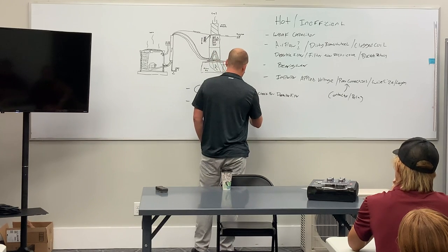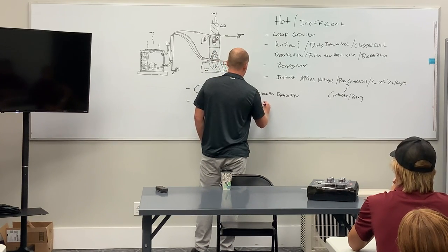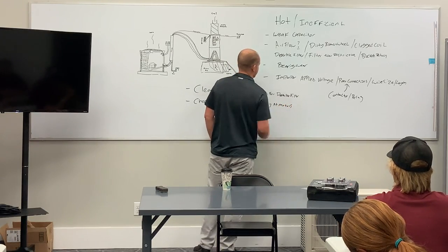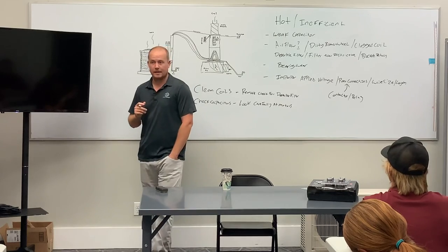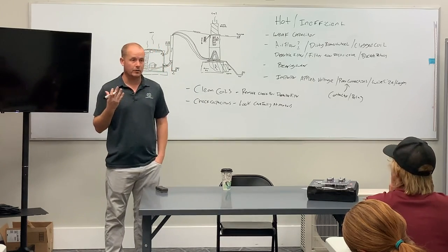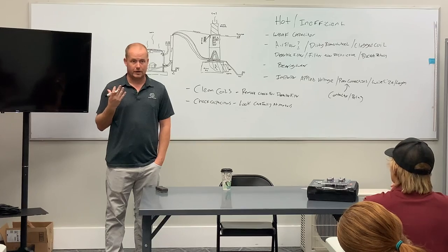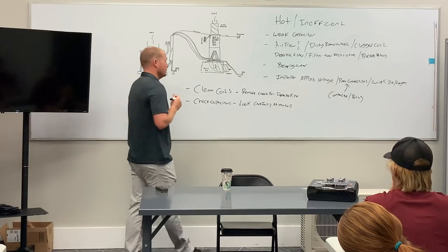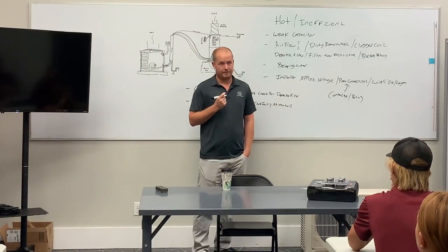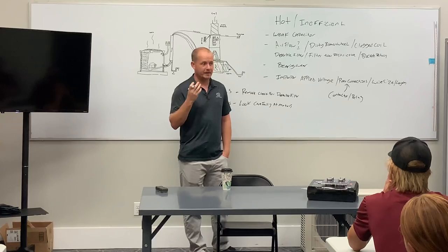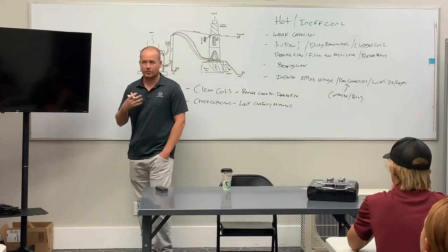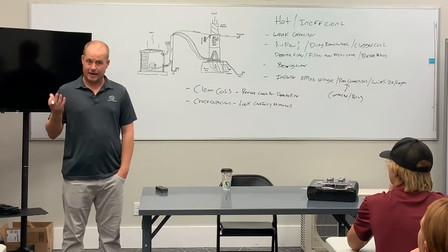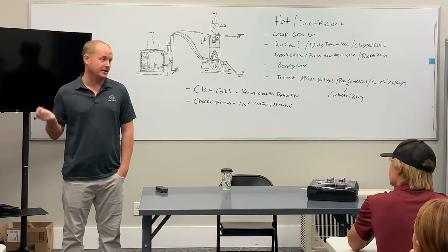Look carefully at the motors. There's another thing that we didn't cover here, but especially on air over motors, like blower motors, even the end bell being dirty can result in that motor running hot and inefficient. If the motor body gets dirty and the air doesn't move through it as easily, that can cause a problem. But also look at the motors for bearing wear. A little bit can be normal as a motor gets older, but when you see a lot of oil leakage at the shaft end of that motor, that's an indication that the motor's losing lubrication, because that lubrication started inside the motor.